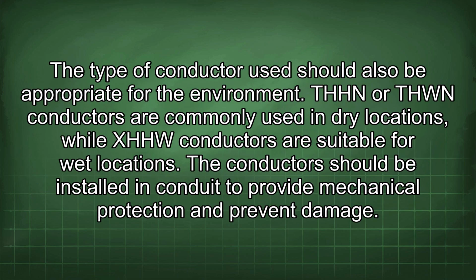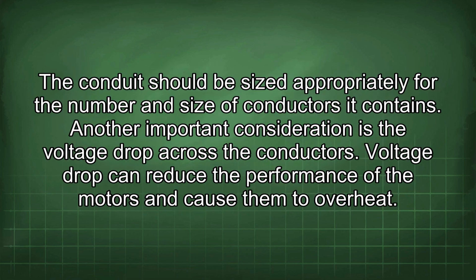The type of conductor used should also be appropriate for the environment. THHN or THWN conductors are commonly used in dry locations, while XHHW conductors are suitable for wet locations. The conductor should be installed in conduit to provide mechanical protection and prevent damage. The conduit should be sized appropriately for the number and size of conductors it contains.